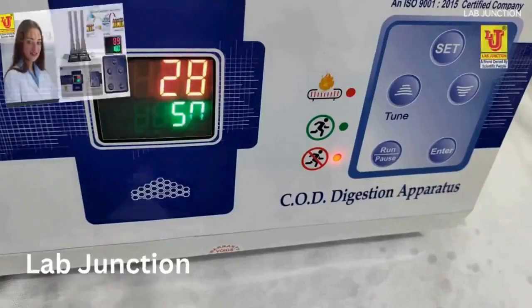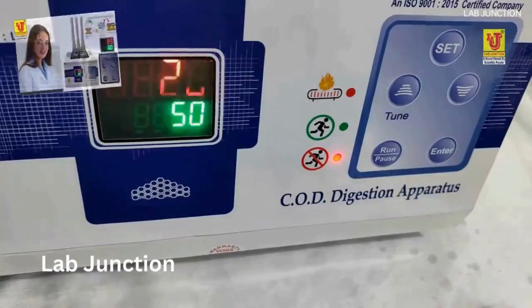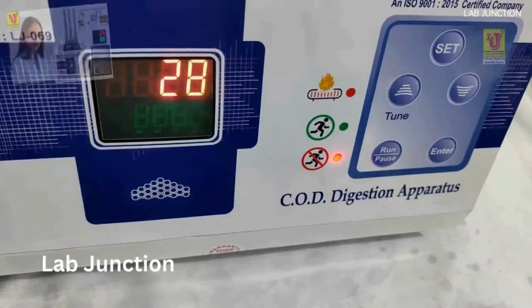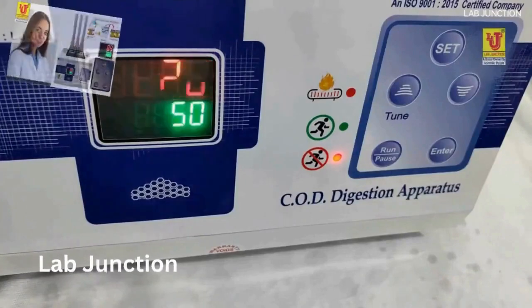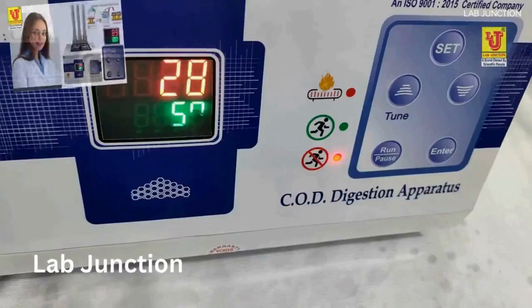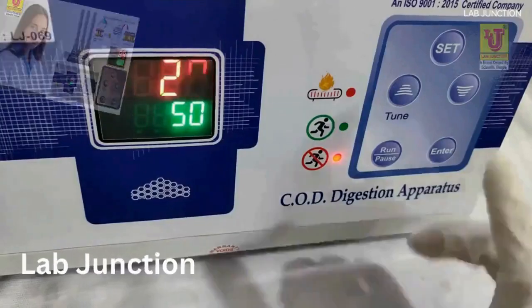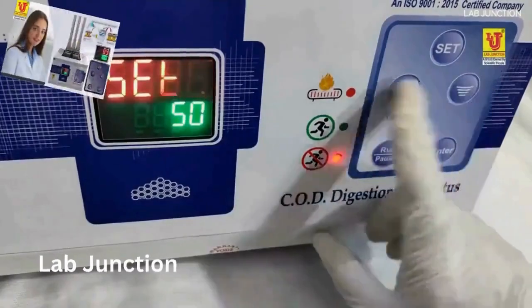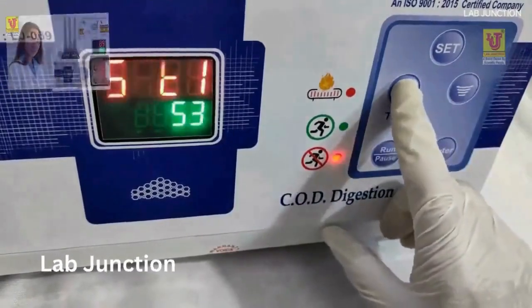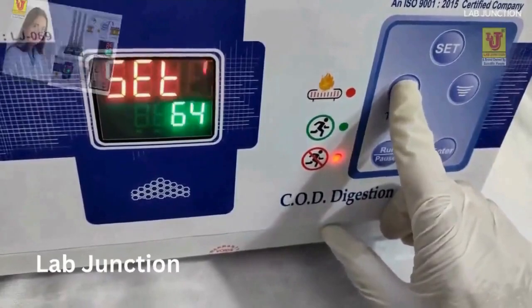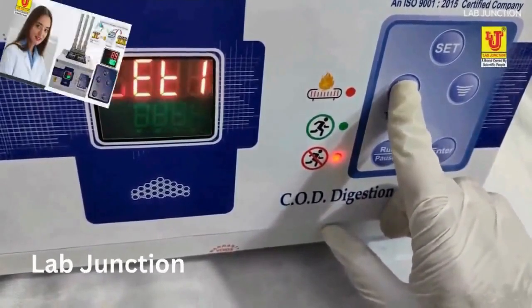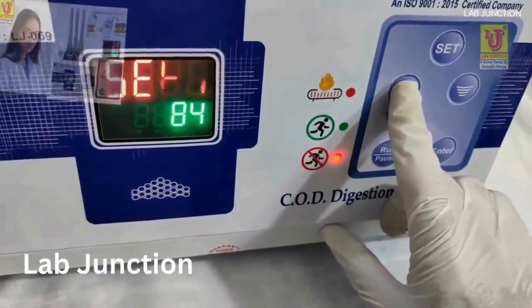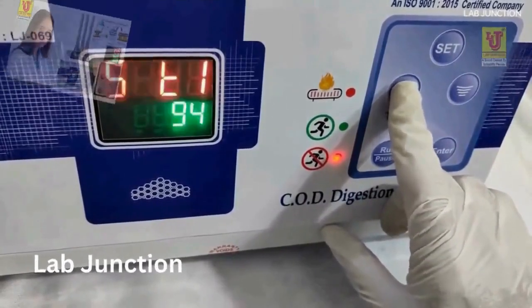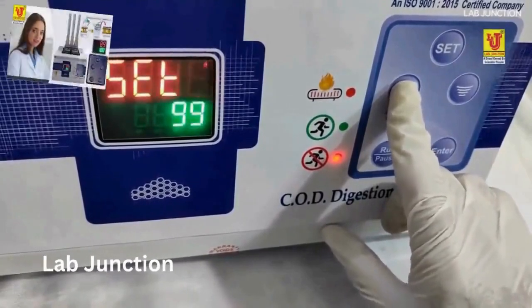display keys? First you have to set your temperature. Its range of temperature is 5 degree to 150 degree centigrade. Now you see, you have to set your temperature, press set key, set one, press up and down keys, you can tune this. Just like I am setting 100. Press enter.